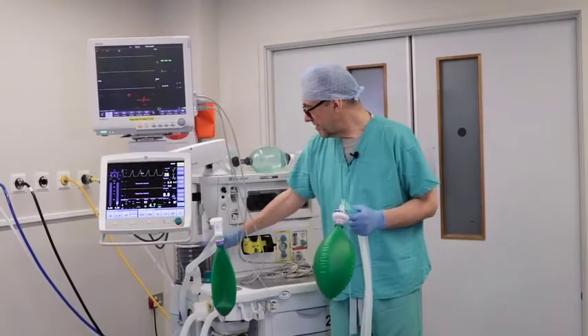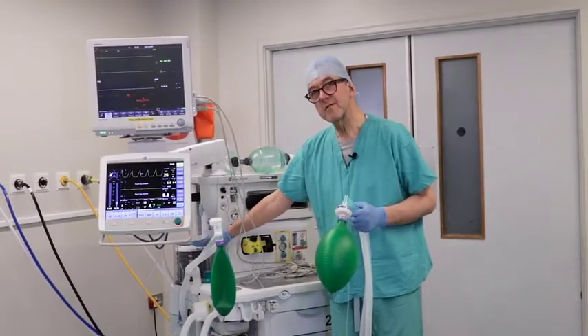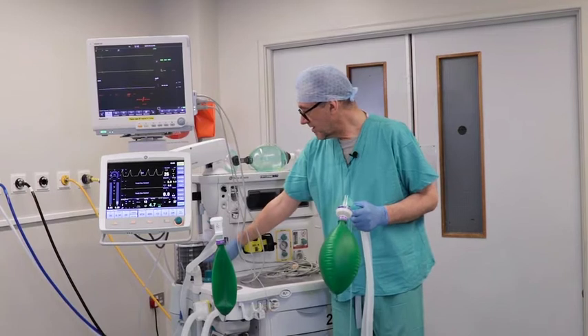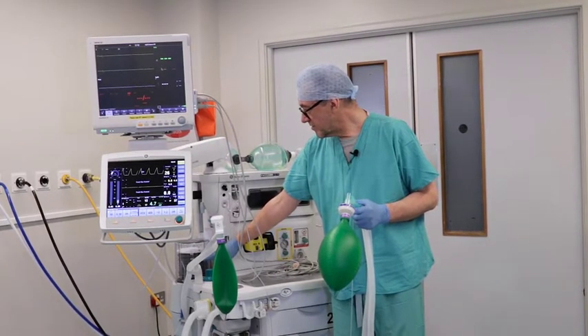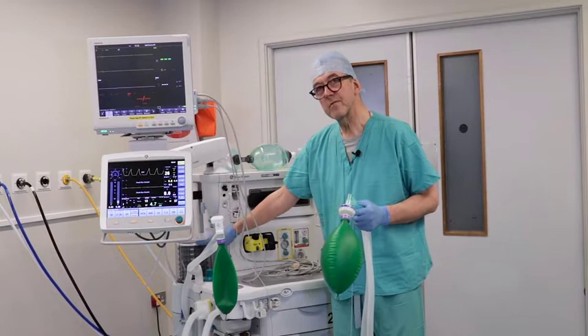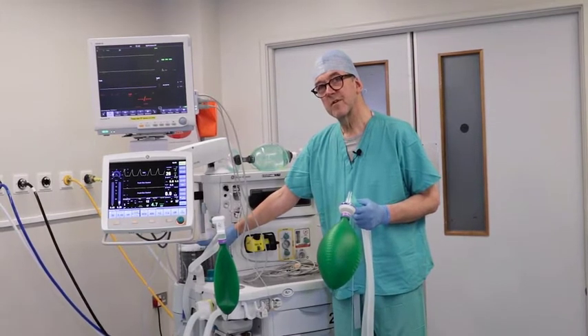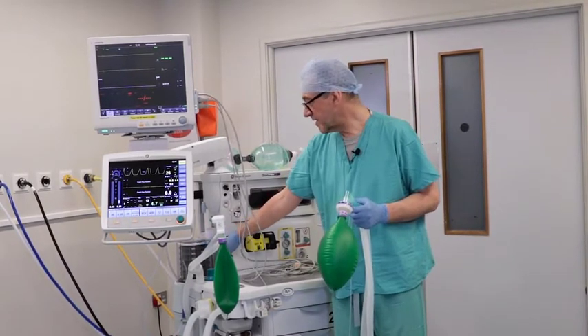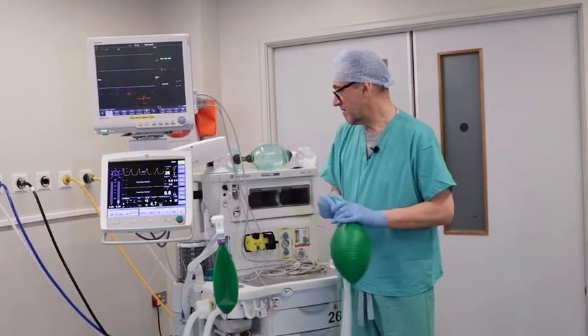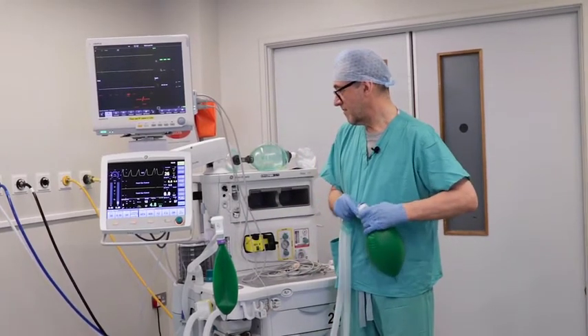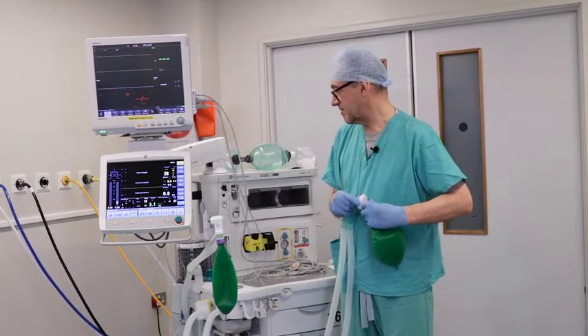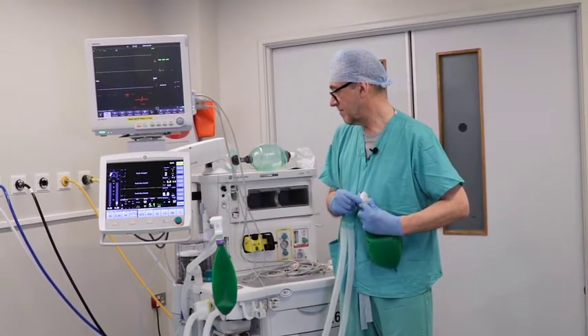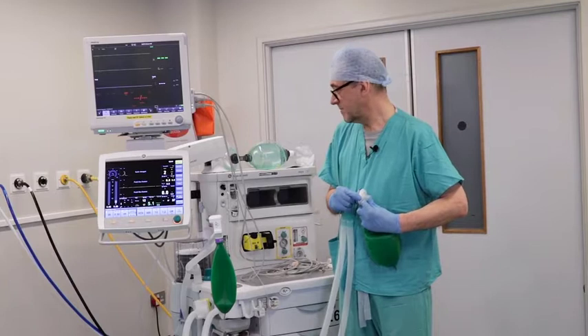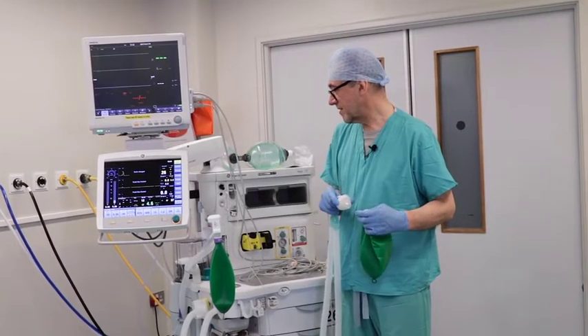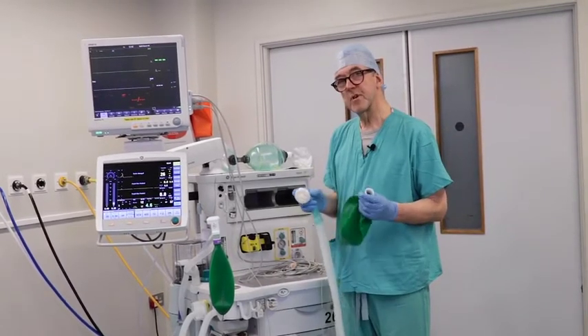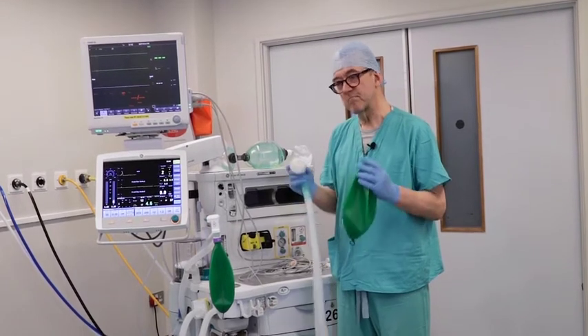So the ventilator is driven by the bellows here, and in normal working, the bellows fall on inspiration and should rise back to the top on expiration. If the bellows don't rise back to the top, that suggests there might be a leak in the system. If the bellows fall altogether and don't re-inflate, then the circuit has probably become disconnected at some point.